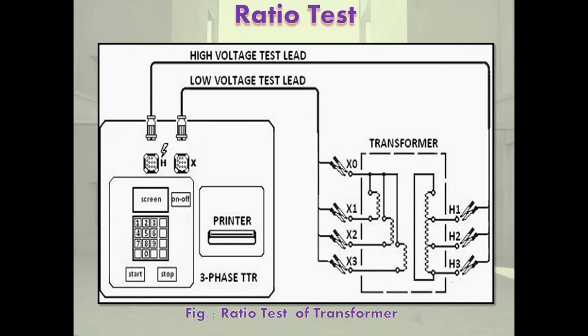After ensuring that the two voltages are in opposition, accurate readings are obtained by an ammeter connected between the two windings, so that the circulating current due to the difference in potential may be detected. Ratio test should be conducted on every transformer, as any ratio error detected in the windings may then be readily rectified. The permissible tolerance is plus or minus 0.5% of the declared ratio. This test should be conducted for the position of every tap.